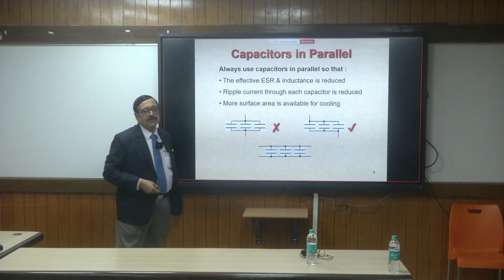One method of making a parallel connection is not correct: the middle capacitor has the minimum wire length, while the two outer capacitors have relatively longer wire lengths. So when an AC component of current flows, most of it will flow through the middle capacitor rather than through the inductance and resistance of the outer capacitors. As a result, that middle capacitor becomes hotter than the others - they are not sharing the load equally.